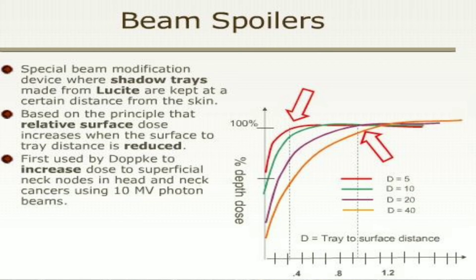Beam spoilers are a special beam modification device where shadow trays made from Lucite are kept at a certain distance from the skin, based on the principle that relative surface dose increases when the surface-to-tray distance is reduced.